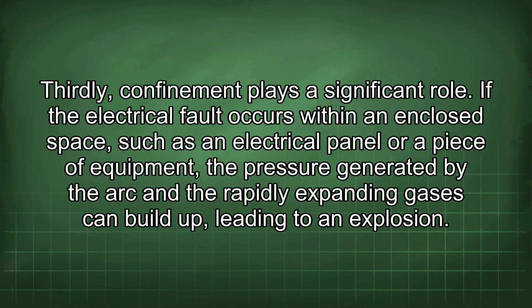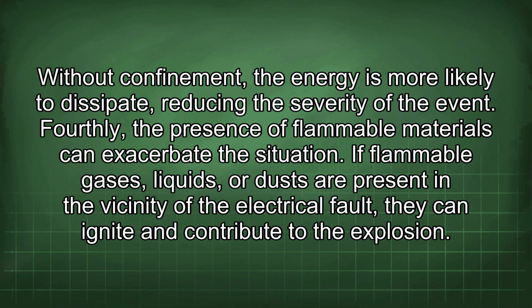Thirdly, confinement plays a significant role. If the electrical fault occurs within an enclosed space, such as an electrical panel or a piece of equipment, the pressure generated by the arc and the rapidly expanding gases can build up, leading to an explosion. Without confinement, the energy is more likely to dissipate, reducing the severity of the event.